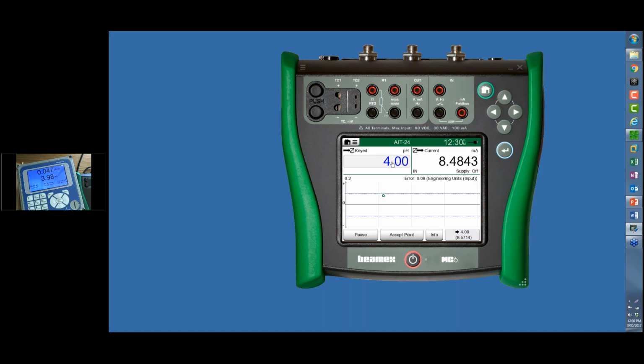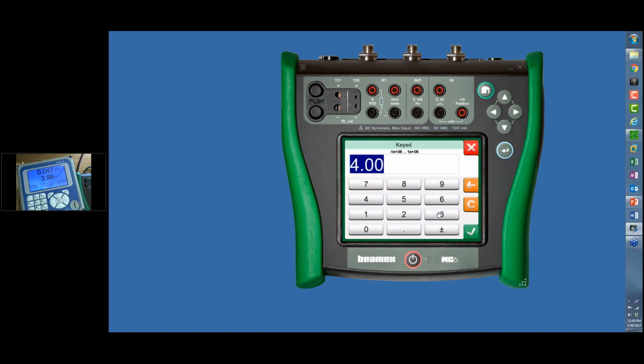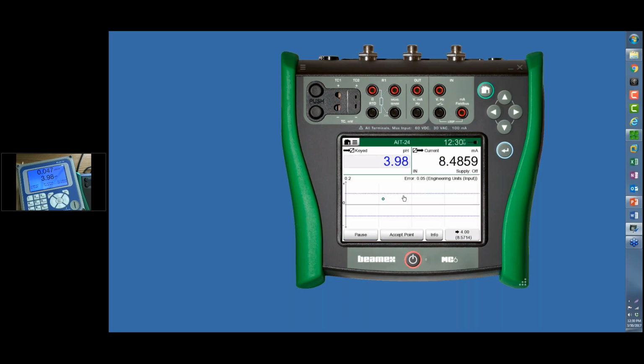So we're measuring what that thing is giving us. So on the calibrator, we actually need to put in what we're seeing on the screen, 3.98. So I'm going to click on the calibrator. This is the keyed in portion, 3.98. And we're measuring the output. Our error is 0.05 pH. So let me accept this point. The next one is our 10 pH.